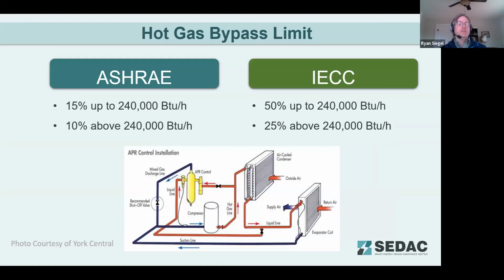So they also treat hot gas bypass a little bit differently. ASHRAE is much more restrictive as far as hot gas bypass. ASHRAE is limiting it to 15%, or even 10% if you're getting into these larger systems over 20 tons. IECC is much less restrictive. It gives you 50% up to 20 tons of cooling and 25% if you're above that.